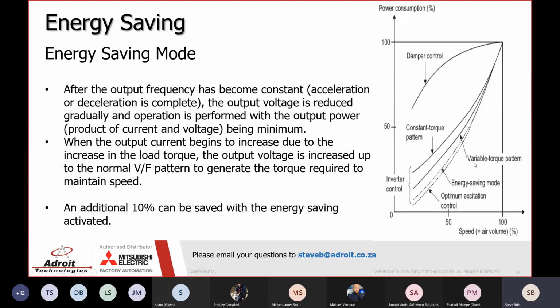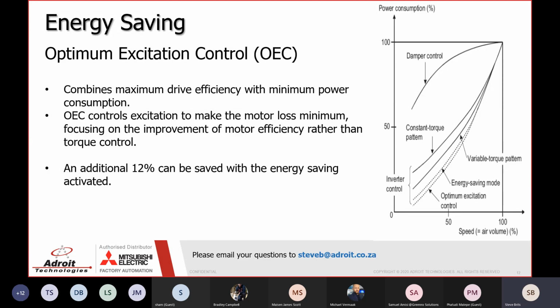If we go to our optimum setting, which is optimum excitation control, this combines maximum drive efficiency with minimum power consumption. The OEC control excitation makes the motor loss minimum, focusing on the improvement of motor efficiency rather than torque control. And this can give you additional 12% energy saving compared to the standard energy saving of 10%, or just by reducing the hertz by 5%.